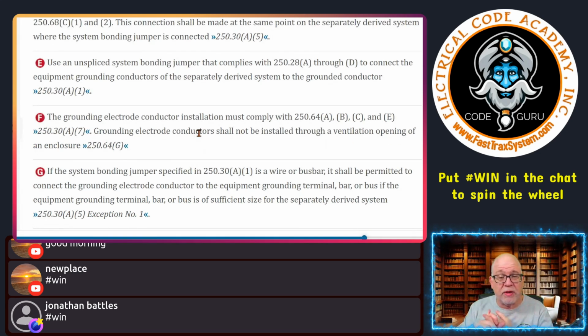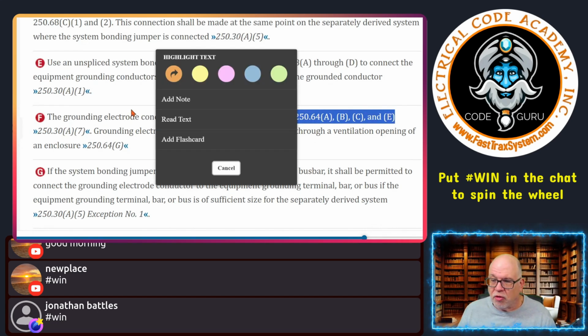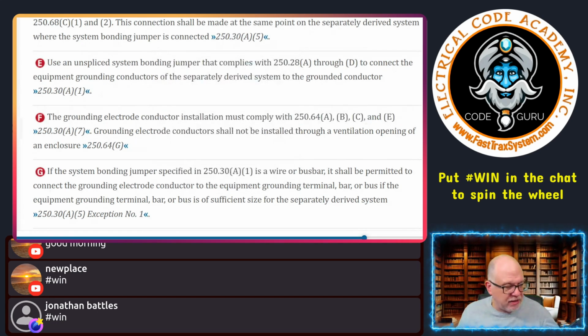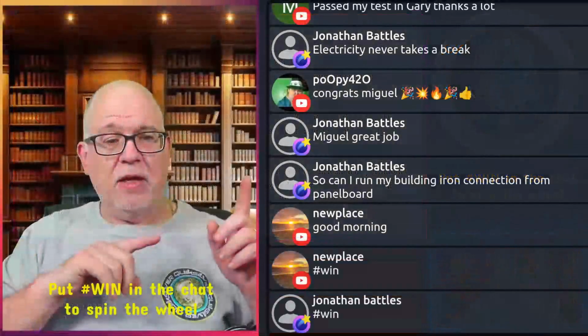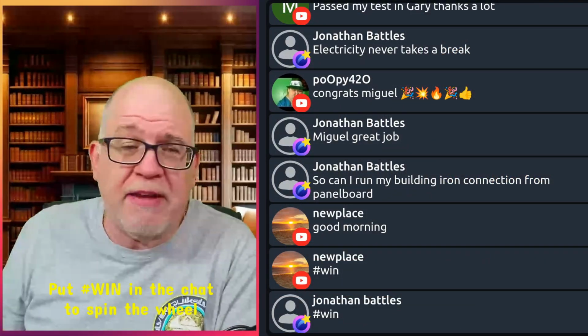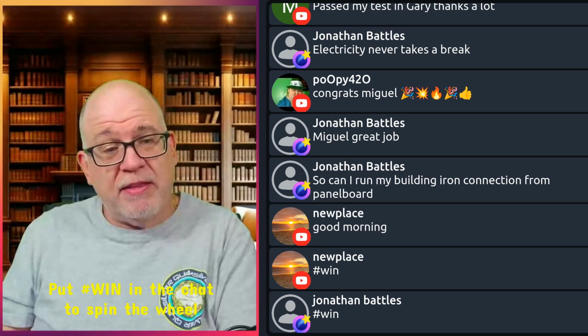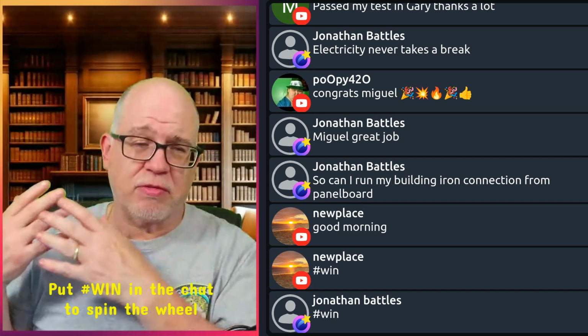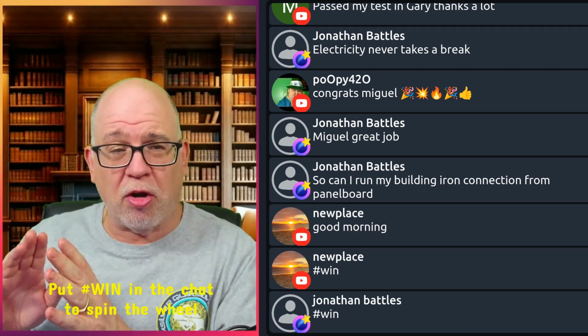Now, what does all this mean? All of that has to do with how it gets from point A to point B in the installation process, remembering that if you're running it through a ferrous raceway, you're going to have to bond it at each end, all those types of things. So those are the installation requirements that you have to meet, and you have to make sure you qualify and meet all of the rules in 250.64(A).